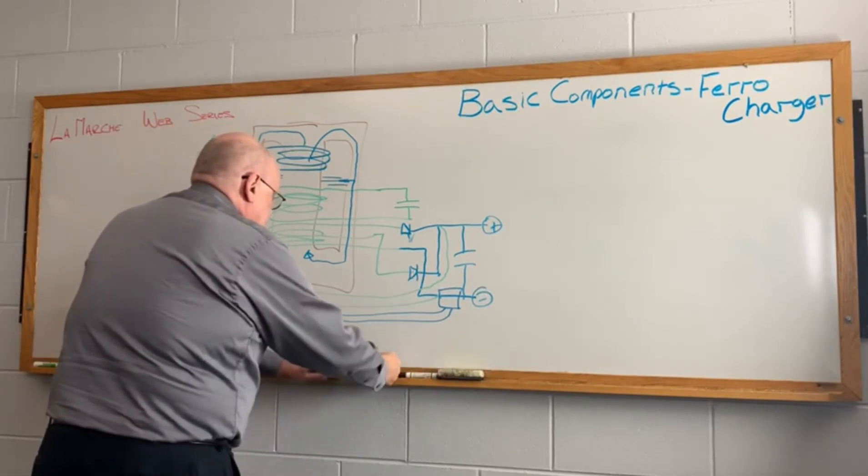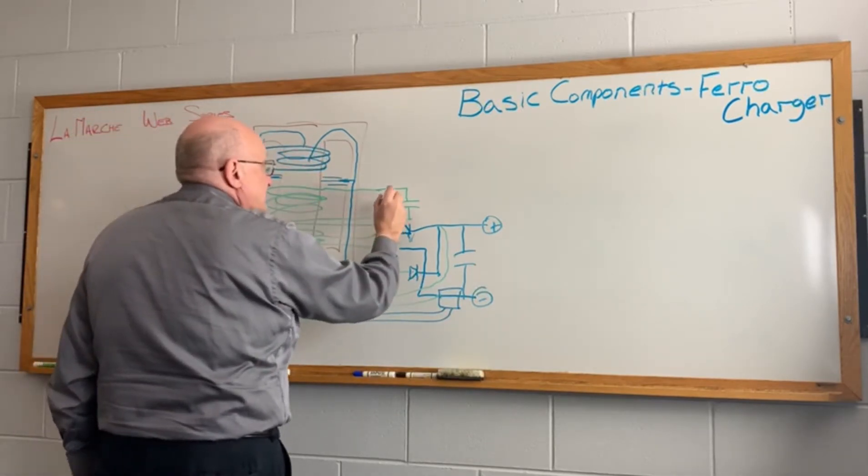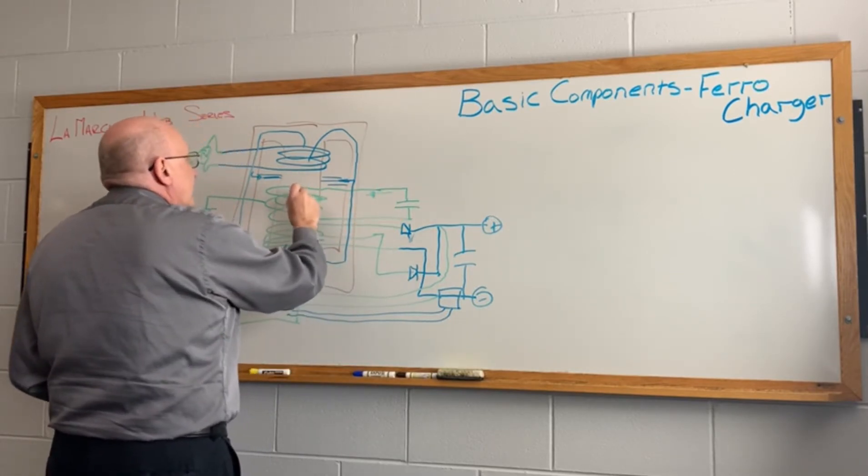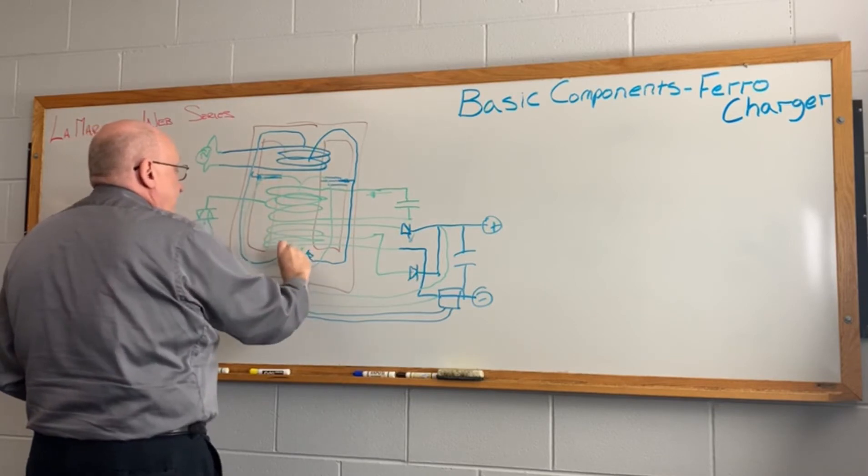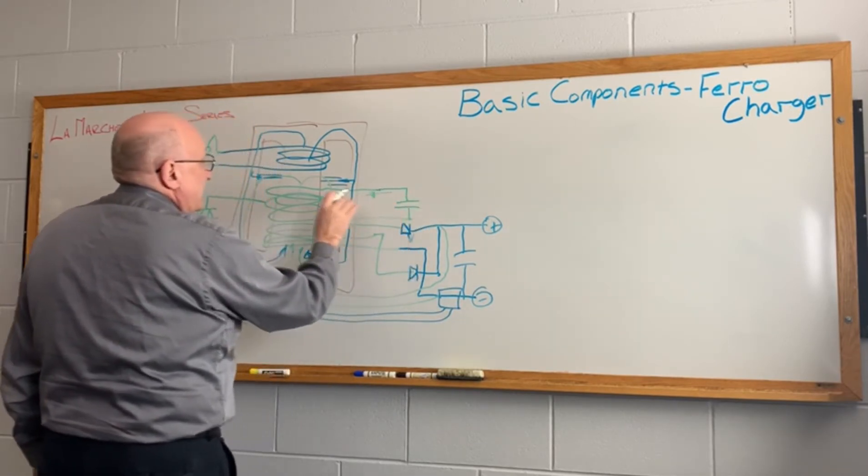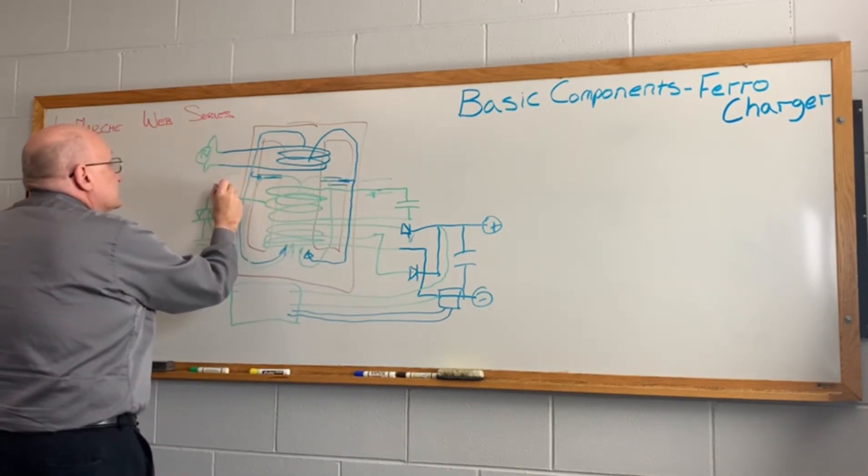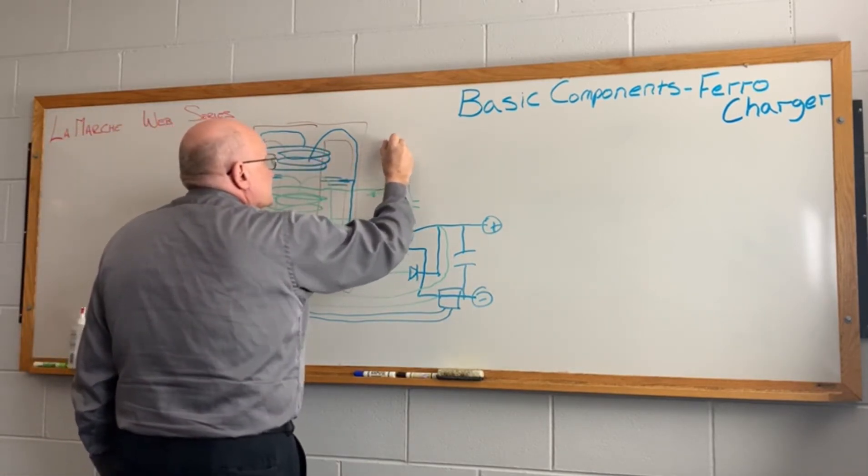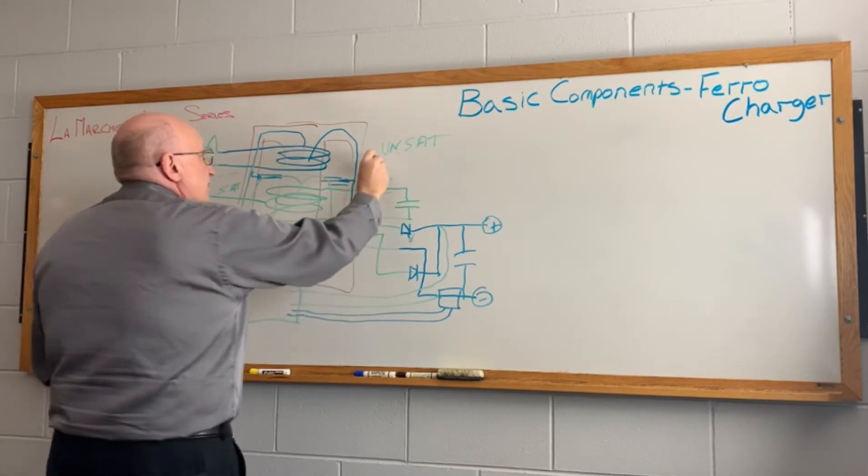What happens next is once we've energized the steel off the primary energy, then translates to the resonating cap. And the resonating cap then will provide a second flux field. It goes this way through the shunt. The resonating cap is meant to provide energy such that the lower part here down the steel is saturated and the primary part is unsaturated, and that's going up that way.